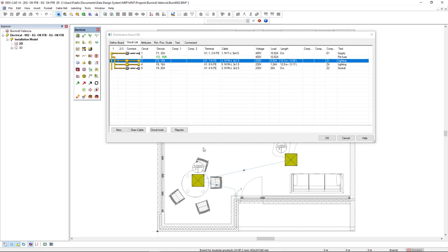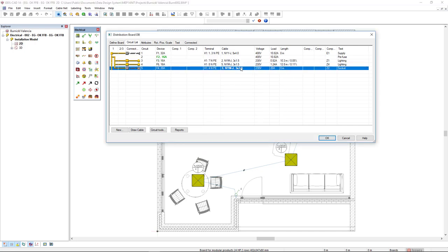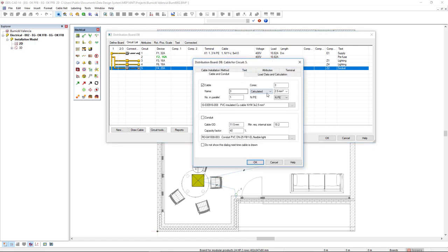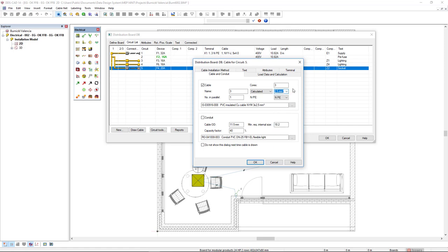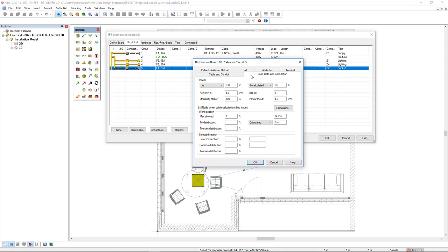We see that for this new circuit, it has been automatically inserted a cable of 3 cores of 2.5 square millimeters. We could manually resize this cable, but to know about the calculation, we go to the tab Load Data and Calculation. By default, the voltage drop maximum allowed is 3%, which allows us to draw this cable for 24.2 meters.